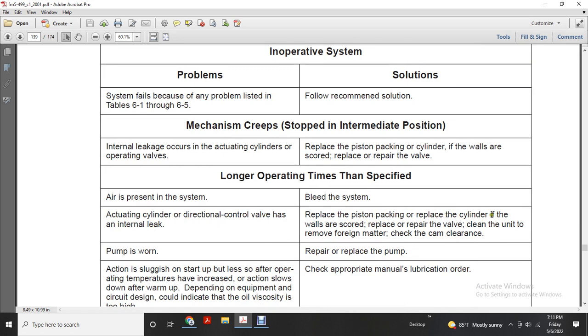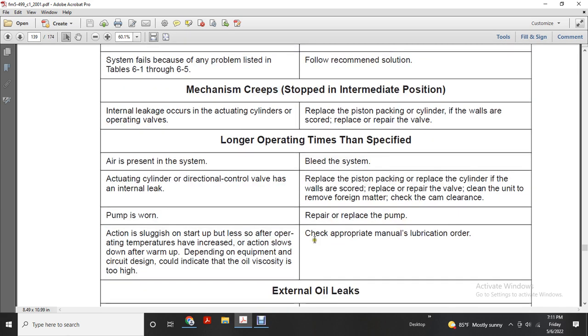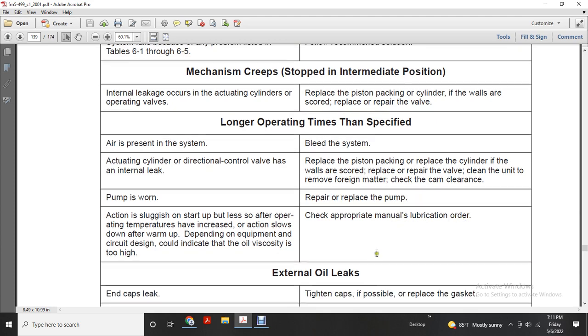Bleed the system. The actuating cylinder or direction control valve has internal leakage. Replace the piston packing. Replace the cylinder if the wall is scored. Replace or repair the valve. Clean the unit. Remove foreign matter. Check the cam clearance. The pump is worn. Repair or replace the pump. Action is sluggish on start up but less so after operating temperatures have increased. Action slows down after warm up. Depending on the equipment and circuit design, this could indicate the oil viscosity is too high. Check appropriate manuals. Lubrication order.